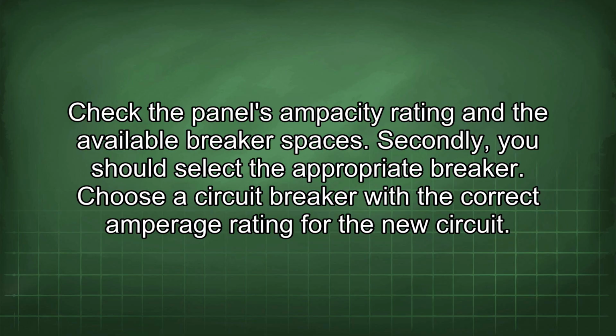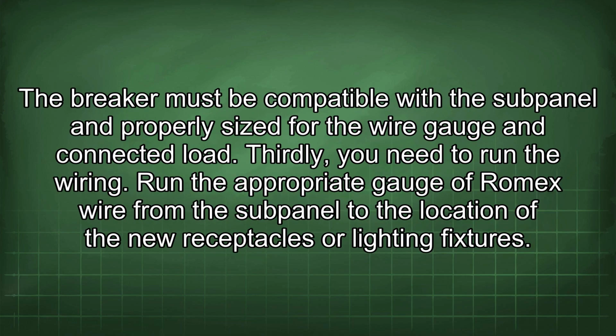Secondly, you should select the appropriate breaker. Choose a circuit breaker with the correct amperage rating for the new circuit. The breaker must be compatible with the subpanel and properly sized for the wire gauge and connected load.